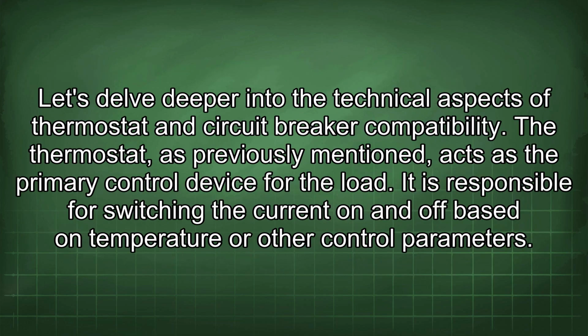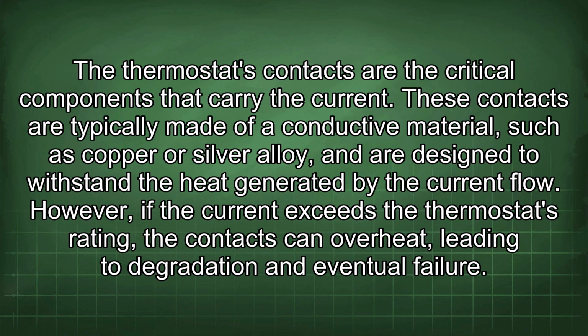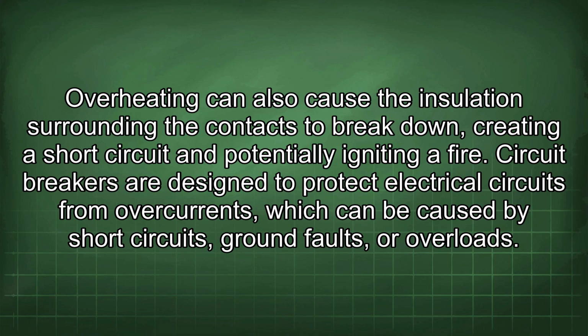Let's delve deeper into the technical aspects of thermostat and circuit breaker compatibility. The thermostat, as previously mentioned, acts as the primary control device for the load. It is responsible for switching the current on and off based on temperature or other control parameters. The thermostat's contacts are the critical components that carry the current. These contacts are typically made of a conductive material, such as copper or silver alloy, and are designed to withstand the heat generated by the current flow. However, if the current exceeds the thermostat's rating, the contacts can overheat, leading to degradation and eventual failure. Overheating can also cause the insulation surrounding the contacts to break down, creating a short circuit and potentially igniting a fire.